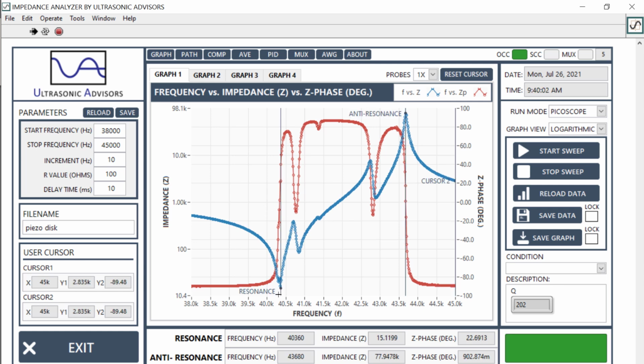for this specific transducer, we can identify the resonance and anti-resonance frequencies. The Q factor is 403, which is consistent with using hard PZT materials and aluminum components. There are spurious modes existing in this specific transducer, which is typically not a positive thing for bolt clamp transducers, but maybe due to some prior use of the transducer. So this would be a perfect candidate for the normal method that I mentioned for extracting material properties.